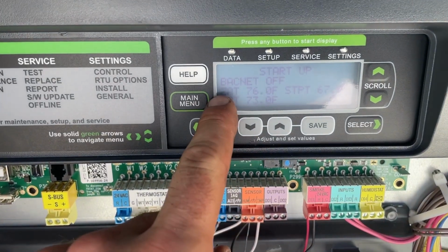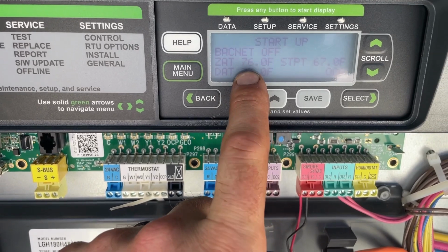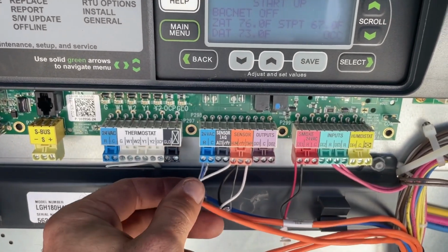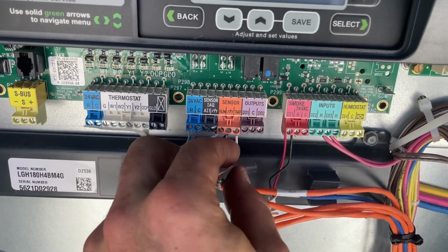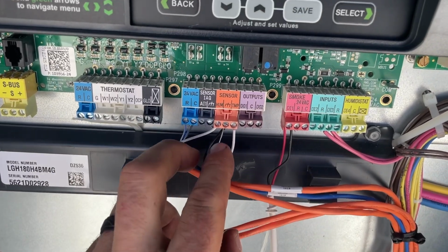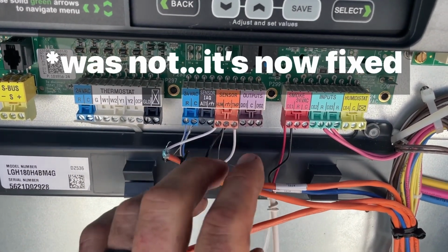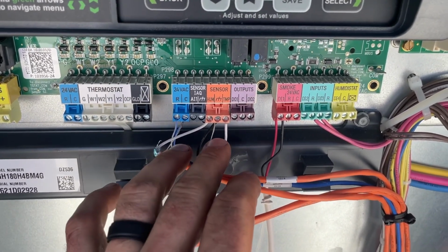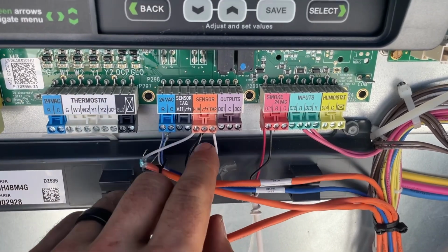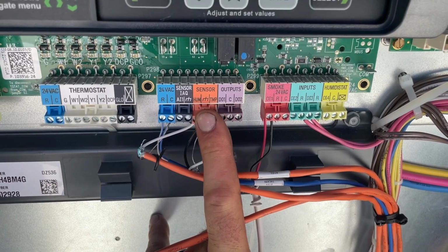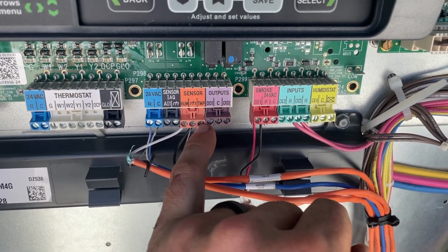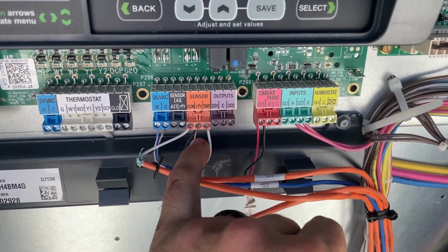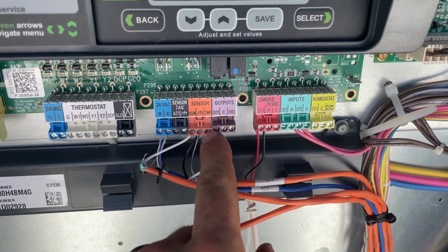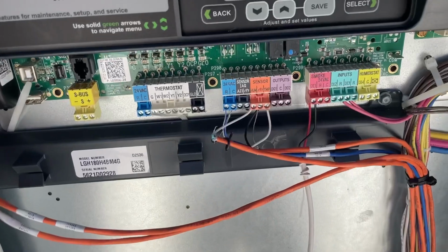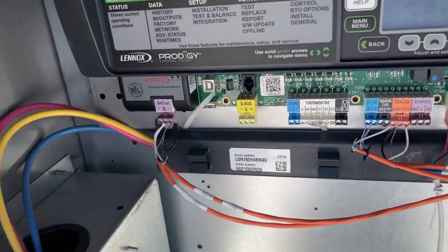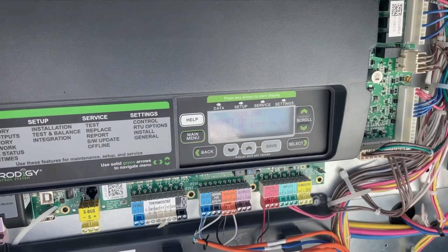All right, I've got my new zone sensor in. You can see it's reading the same as the old one, within reason. Also, you may have noticed in the video, I didn't notice till I started really looking down here, this shield is not correct. Well, first of all, I don't even really think you need a shield because this isn't a comm line, okay? But I'll leave it there. But see, this pin here has direct connection to ground, so the shield needs to go here. I don't know why whoever installed this, it was not us, put the shield up here on the active pin. That can definitely short out your temperature sensor. So I fixed that. Fixed it downstairs as well. All right, doing good.